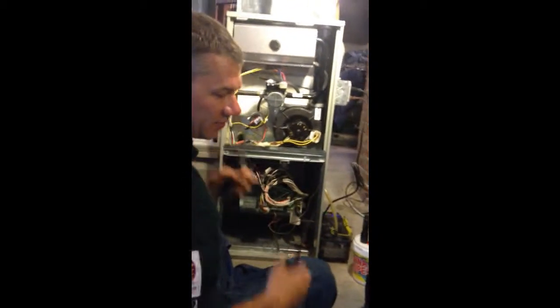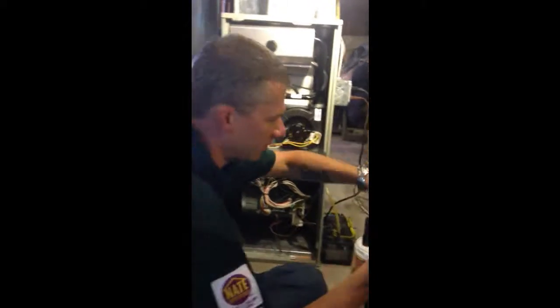What we're looking at, CO is carbon monoxide. When you're running it, that's our parts per million. And if it goes over 100, we've got a red tag. It means there's a hole in the heat exchangers, which was the rust earlier that I was worried about. So we're going to watch that thing and see how high it goes while I'm writing this down. Monoxide output was only 12 parts per million, which is pretty low. Normally I see it anywhere between 10 and like 22 or 23.